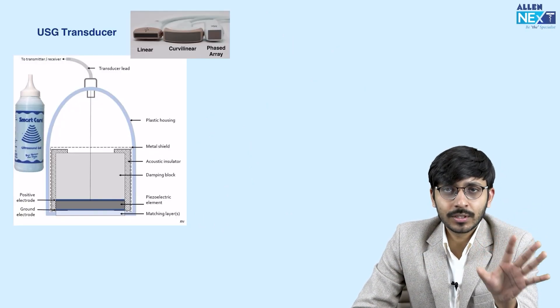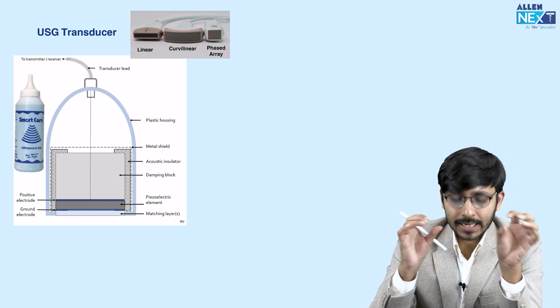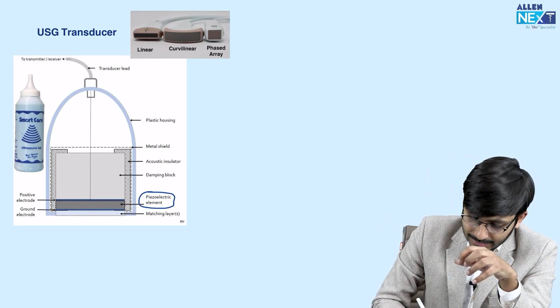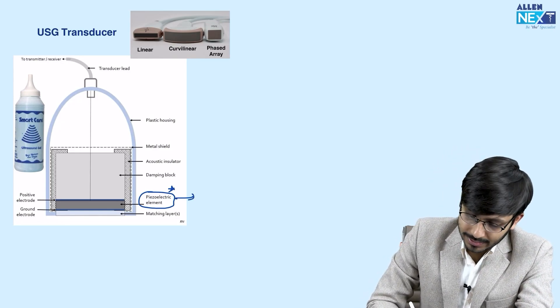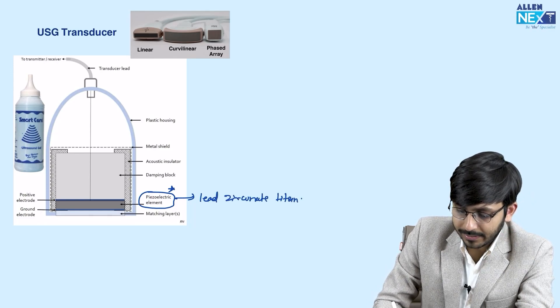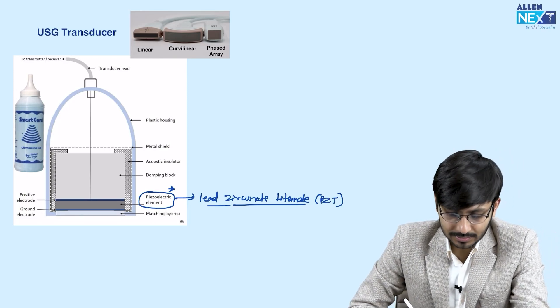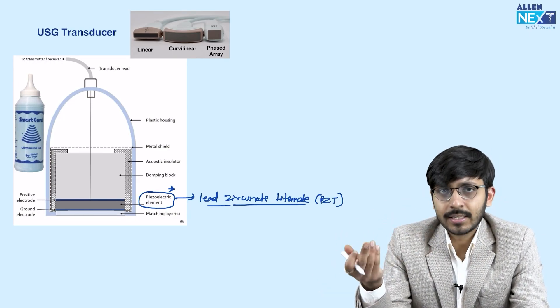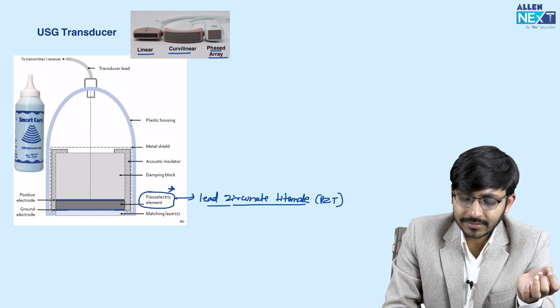Coming on to the main ultrasound transducer, which is the backbone of ultrasound imaging. This is a diagram of an ultrasound transducer, and the most important structure in it is the piezoelectric element. The material it is made of is lead zirconate titanate, also known as PZT. There are different types and shapes of ultrasound transducers — they can be linear, curvilinear, or phased array ultrasound probes.